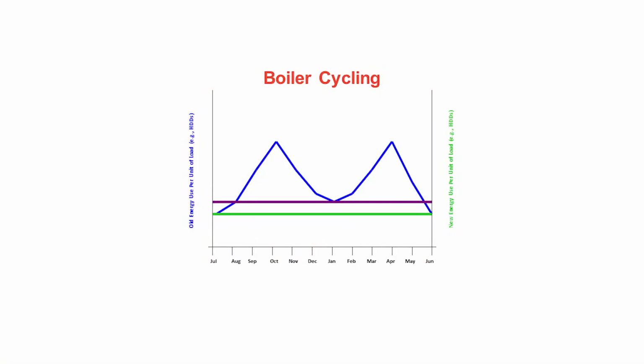So if we could maintain that best efficiency line year-round, meaning solve the cycling problem, we would capture a lot of energy savings. There's a purple line that touches that middle bottom point. That is, I flatlined my efficiency. I said, well, this existing plant can do 84%. We solved the cycling problem, therefore it runs at 84% all the time. We don't have the cycling problem. Now if you said, let's also go with a condensing boiler that can modulate, and we can get cold returns, which makes our efficiency better than that 84%, we can get up to maybe 90%. That would be this green line. We can get even better, and we capture a little bit more savings.